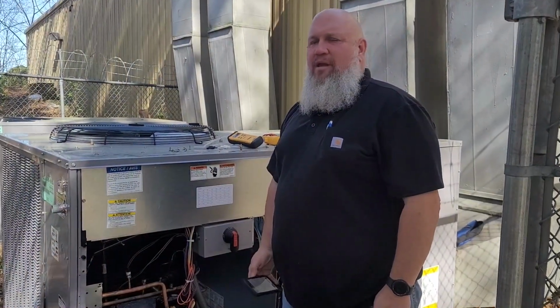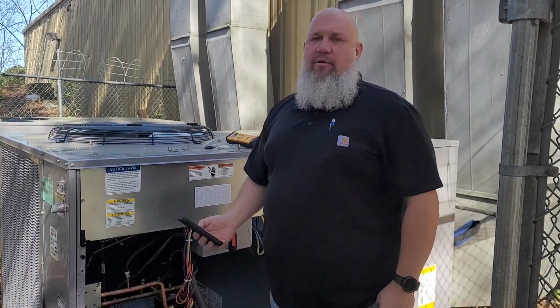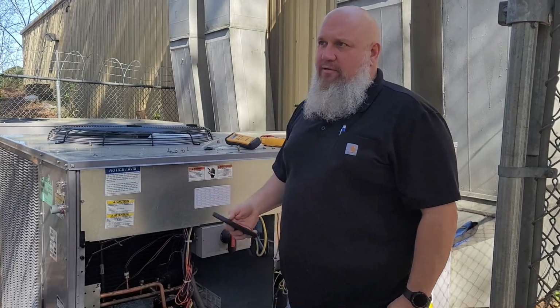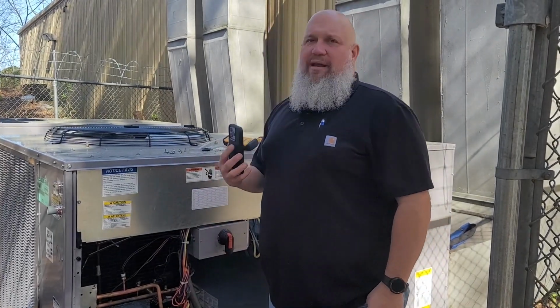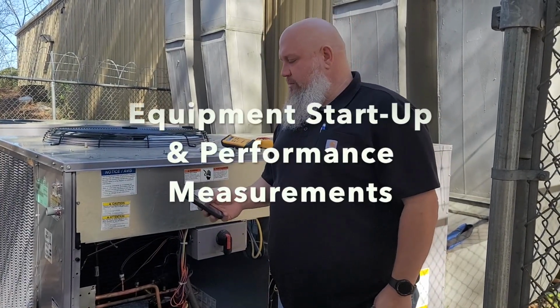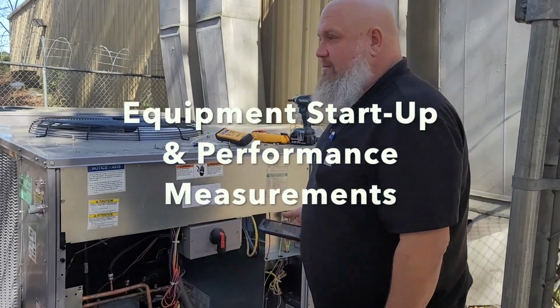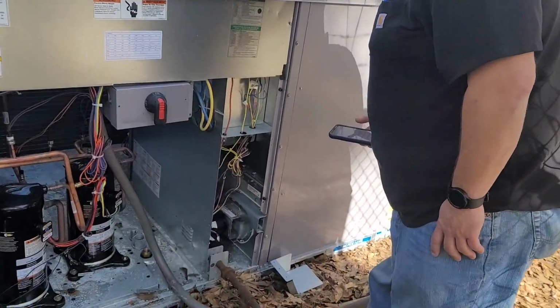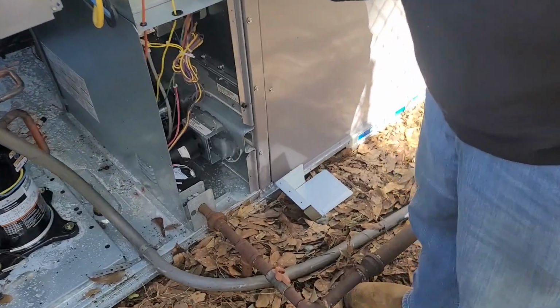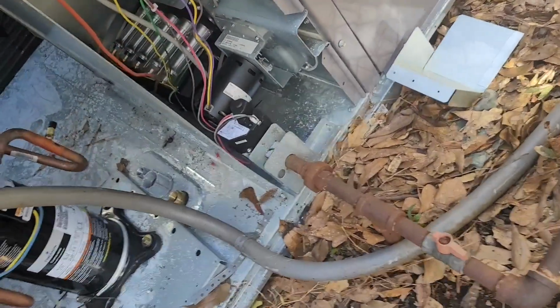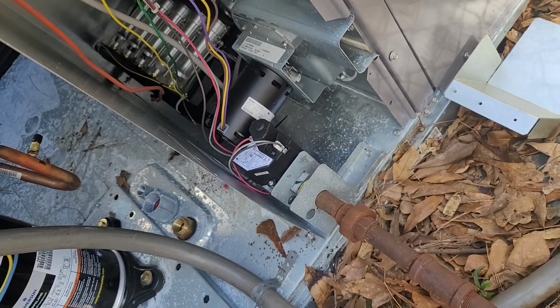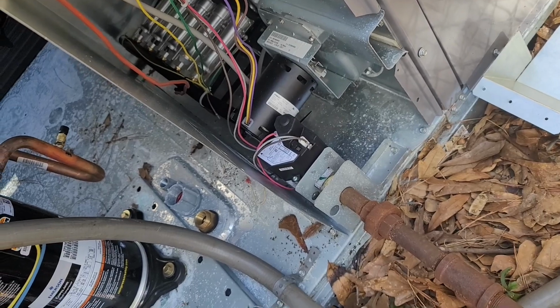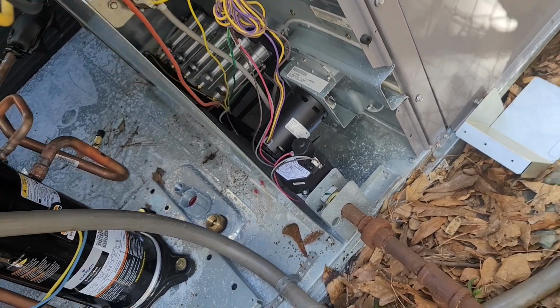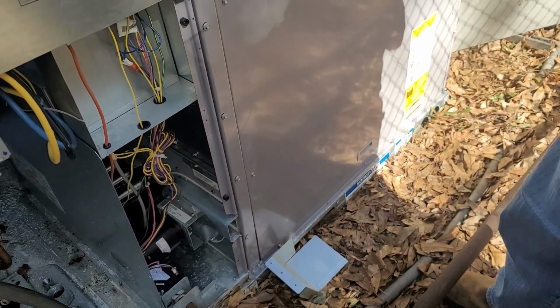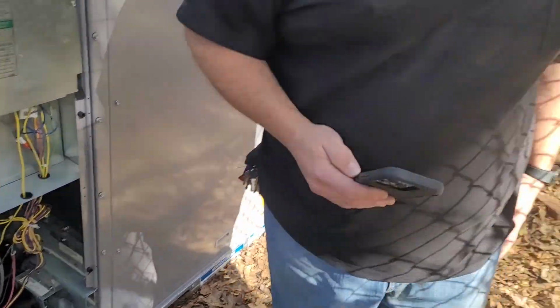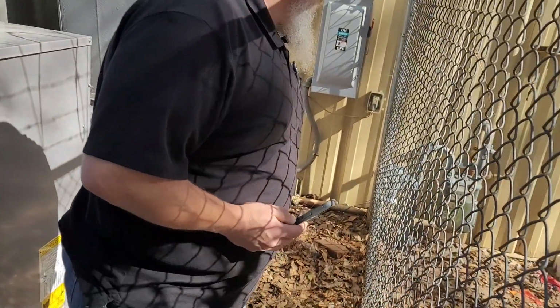What's next on DigiMEP? We've gone through, taken the pictures of the unit, did our assessment of the installation quality, and now it's time to start taking some measurements. First on the list is gas pressure, and unfortunately this one does not have a tap to test the inlet pressure and the outlet pressure. So we're going to have to skip that and make a note. But you can always check your gas pressure at the meter if you've got a tap on it.